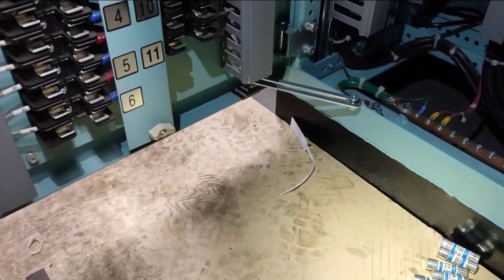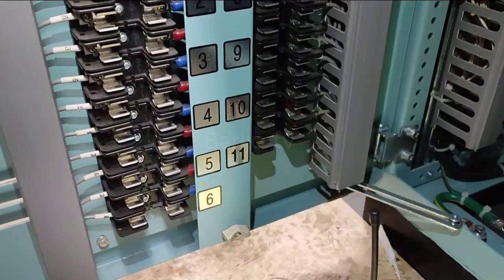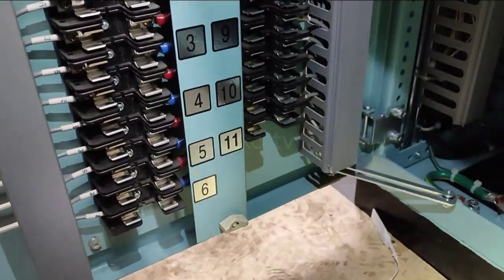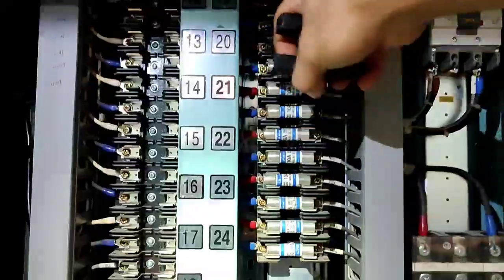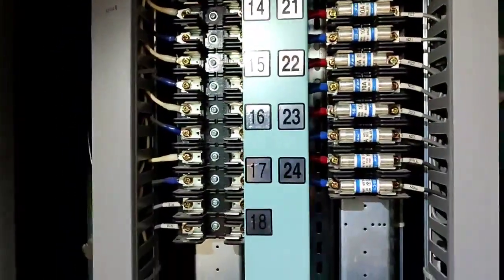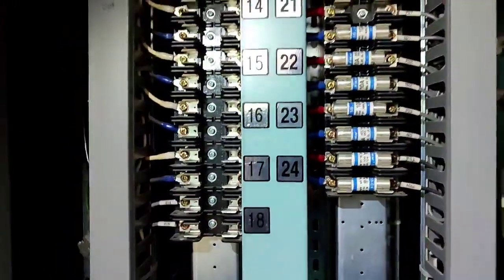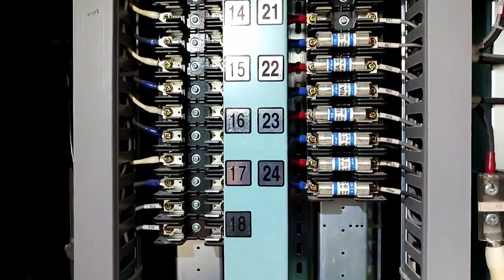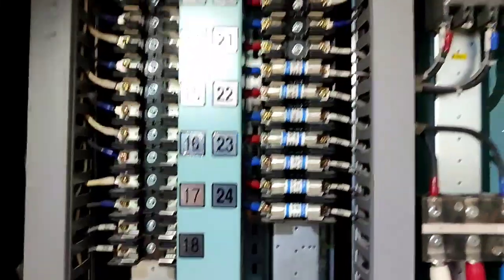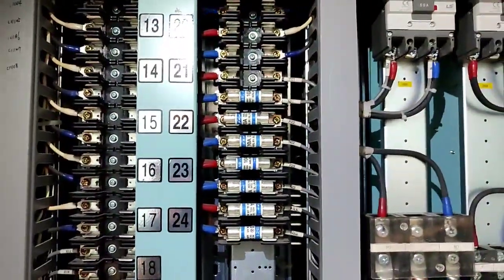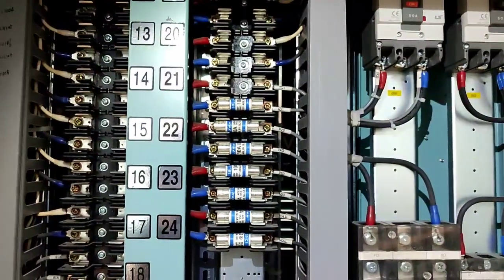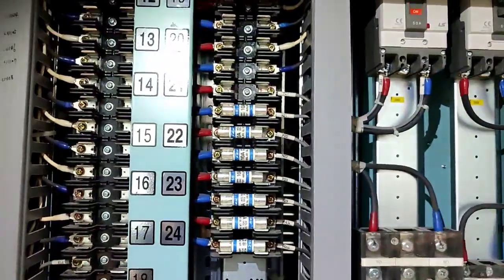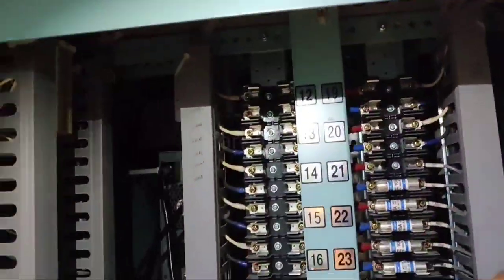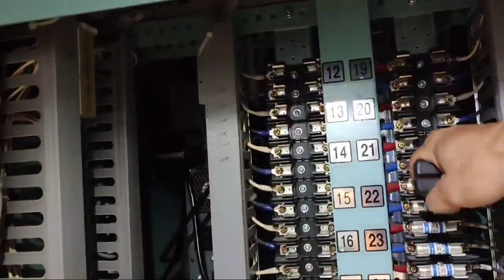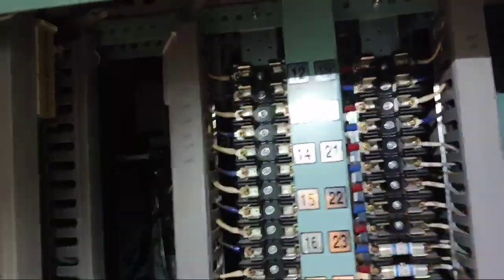Please observe this number 20 fuse. Okay, just watch it. Almost there, sir, going toward infinite. So it is at infinite now. As you notice, we stop at number 20, because we located the low insulation at number 20.